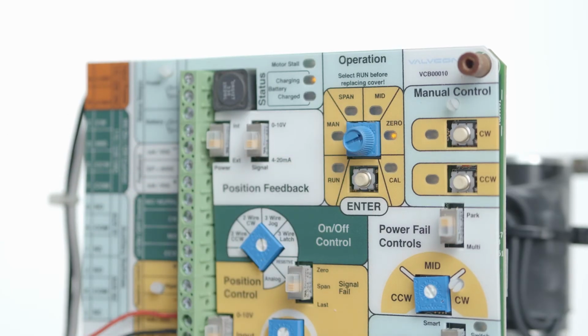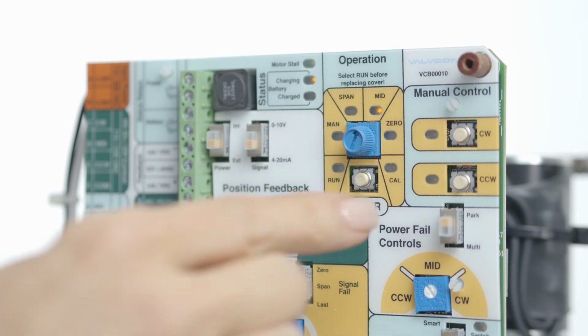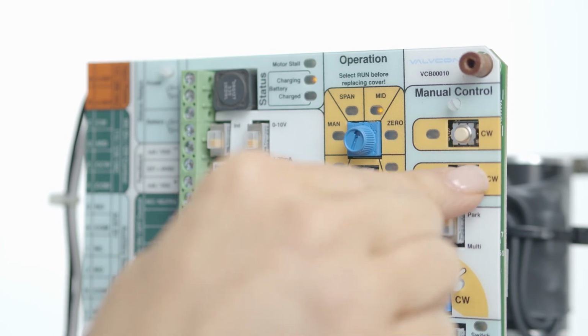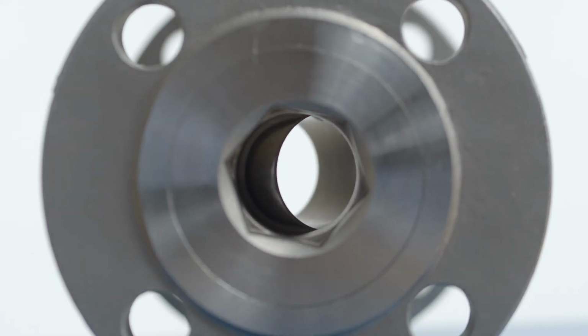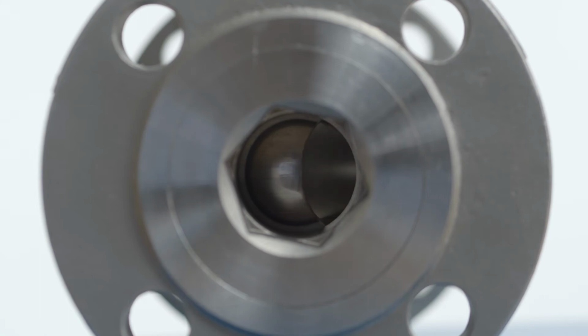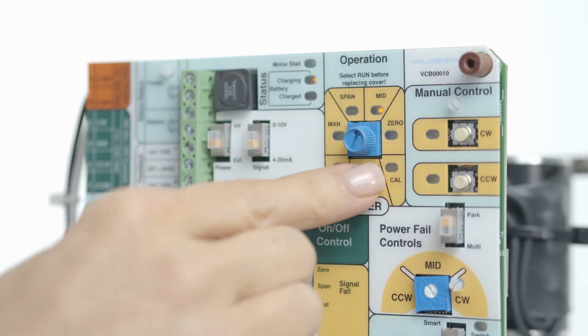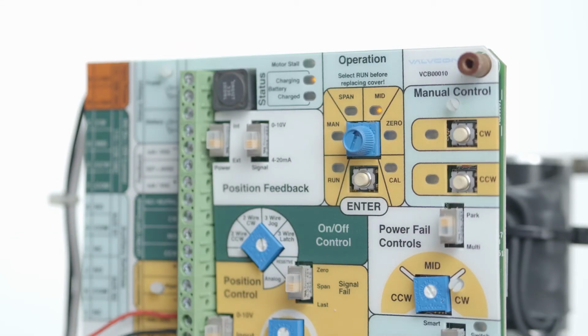To set the optional mid position, this would only apply with 3-wire jog on-off control mode. Turn the mode selector dial to mid and press Enter for 2 seconds. The mid LED will begin to flash. Drive the actuator to the desired mid or third position using the CW or CCW push button. Press the Enter button to save the mid setting.